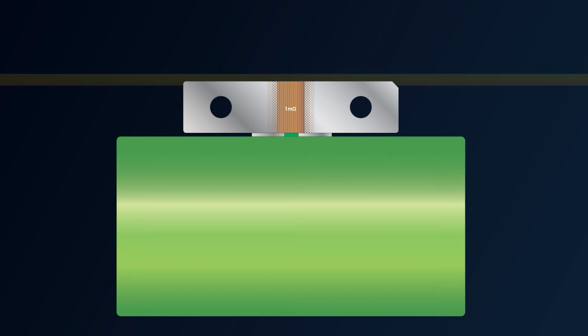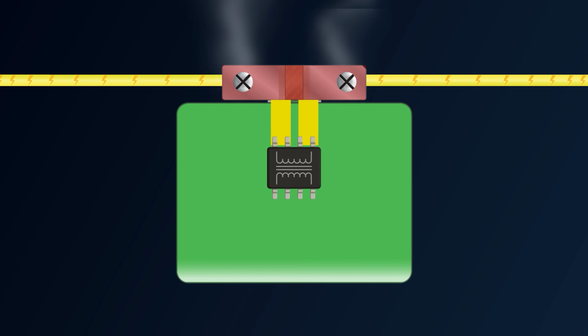The shunt is basically a very precise piece of metal with a known ultra low resistance. It is placed directly in the path of the high voltage cable. As the current flows through it, it creates a tiny voltage drop, and we use Ohm's law to calculate the current. However, because we are physically touching the 800 volts line, we can't just plug this into a BMS. For that, we have to use an isolation amplifier to get the signal. Well, shunts generate heat. If you push high current through even a tiny resistance, that metal gets hot. Like very, very hot.